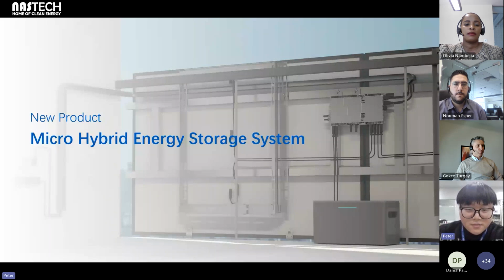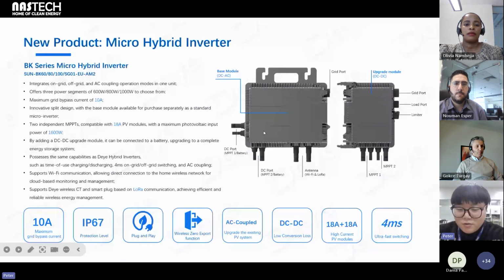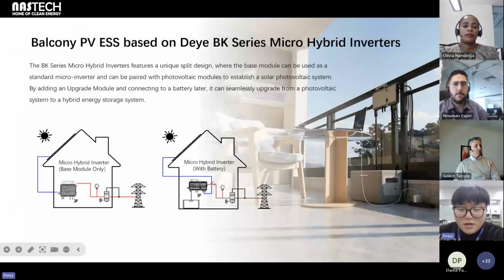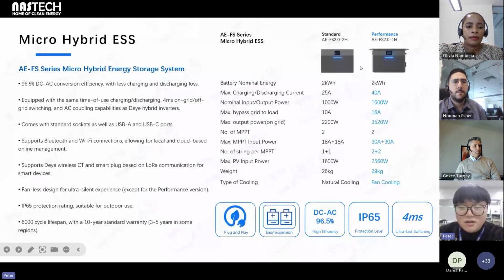The micro hybrid system. Actually, you can use the regular module as a regular microinverter, and when you plug in the upgrade module, you can connect the battery, and it can be upgraded to a micro hybrid system. It still has the IP67 proof level, and it also has 4 millisecond faster switching. This is when it uses a base module and a module with a battery. And we also have another solution, an all-in-one solution. It has a battery together with a microinverter, with basically the same features, but in an all-in-one design, and you can see a small screen above.